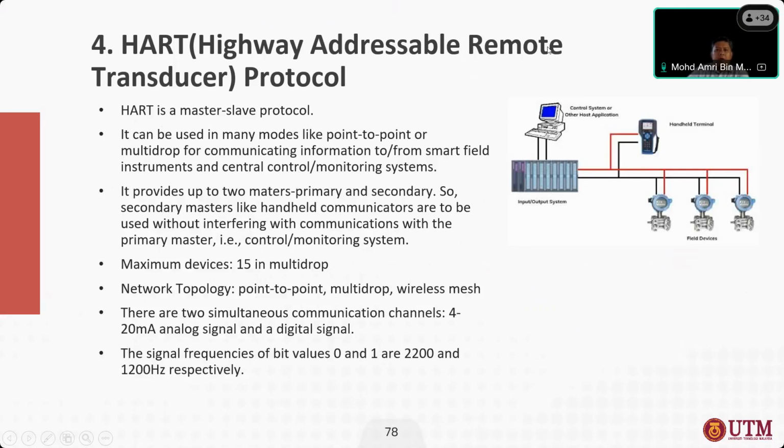Then we have Highway Addressable Remote Transducer protocol, or HART. Okay, HART is a master-slave protocol. It can be used in many modes like point-to-point or multi-drop communication for smart field instruments and central control monitoring systems. It is usually used to communicate or connect with instrumentation devices.